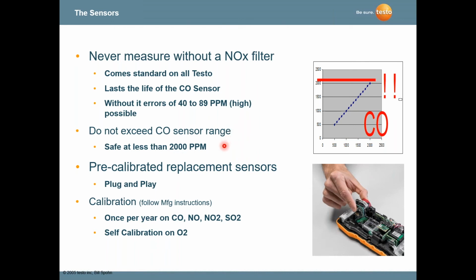Keep in mind that we're measuring hundreds of ppm or less in the flue gases, not thousands, and we're certainly not in ambient air. So if you're reading 1,000 ppm CO, pull the probe out immediately, because you have a condition that will take some time to figure out. Pre-calibrated sensors are a big deal today; they're plug-and-play. We recommend calibrating our sensors once per year. These are the toxic gas sensors here.